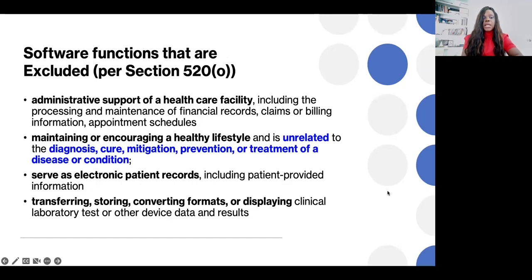Next slide, please. So software functions are actually written in section 520 of the Act. And in this section, the FDA states that if you have software that's for administrative support only for a healthcare facility, for example, including processing and maintaining financial records or claims or billing information or appointment schedules, this is actually not considered a medical device. Also, if the software function is for maintaining or encouraging a healthy lifestyle, this is not a medical device, but it has to be unrelated to diagnosis, cure, mitigation, prevention, and treatment.